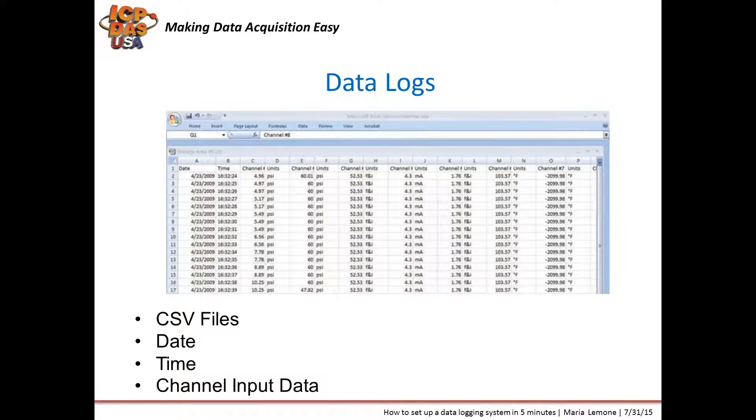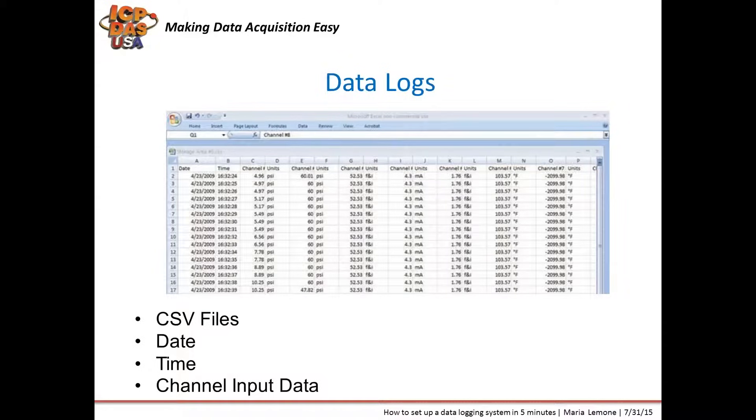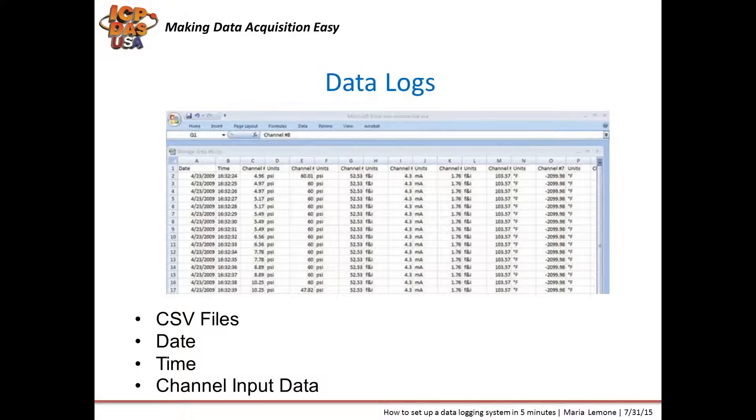On CSV separated value data log files, you can see the time, date, and measurement values. You can log data at various intervals like every second, every hour, or every day. The sampling rate is determined by your network and data acquisition equipment. Our equipment can be logged at up to 60 samples per second. This data log here is from 2009, and it shows sampling of pressure, current, and temperature taken every second.